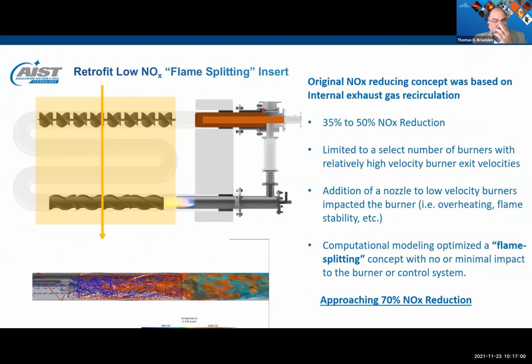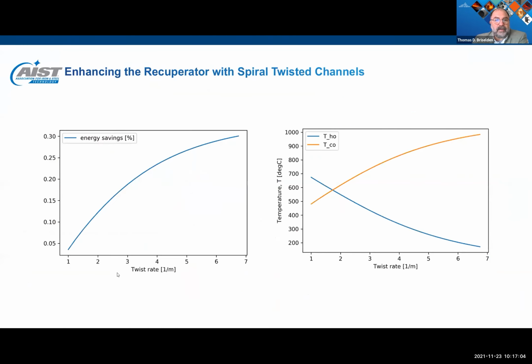This gives an example of how energy savings is impacted as we increase twist rate and thus the surface area of the heat exchanger. And then also the changes in combustion air preheat as a function of the twist rate of the heat exchanger.